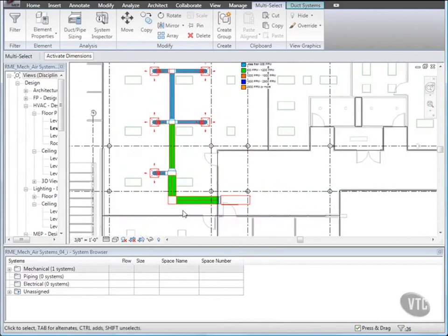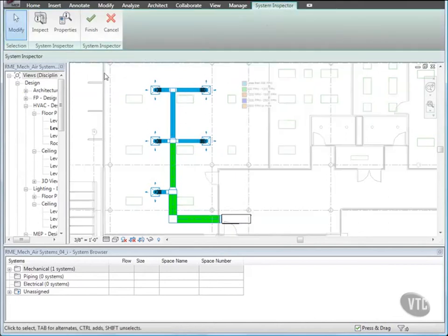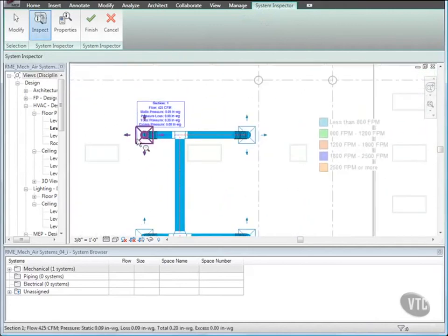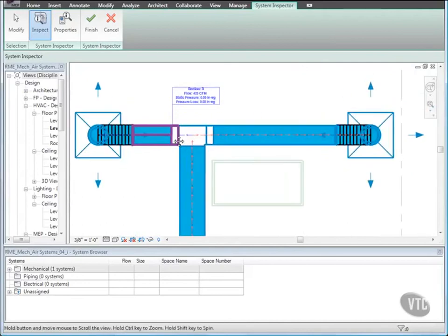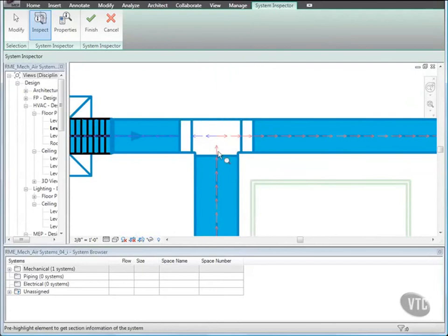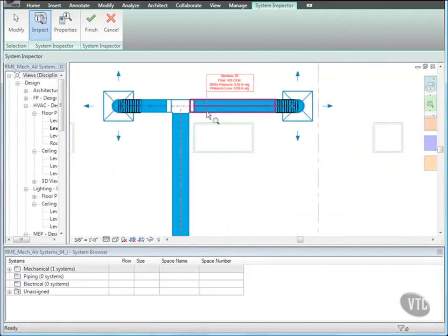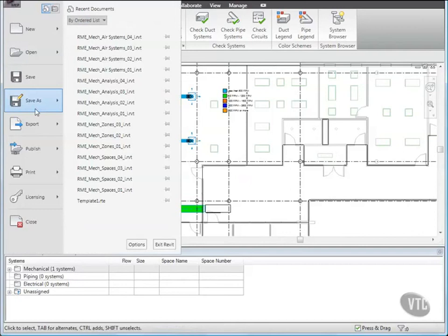Next, select one of the ducts in the Supply Air System, and click System Inspector. Then click Inspect, and move the cursor over the system components. You can use the information that displays — flow, static pressure, and pressure loss — to find deficiencies in the system so that you can modify the system design accordingly. Remember that all information is color-coded according to pressure. Red information and arrows indicate the highest percentage of pressure loss due to friction, also known as critical path. When finished, click Finish. Then close the file without saving any changes, as the next lesson will provide its own training file, and that concludes this lesson.